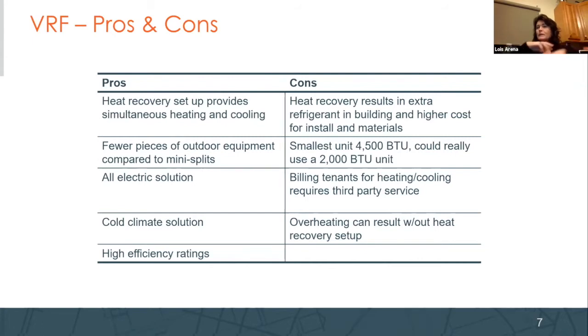So you need a heat recovery system to be able to achieve that. If you don't have that ability, you're basically in what they call heat pump mode, where you're either in heating or you're either in cooling if you're all on that same condenser. You can have fewer pieces of outdoor equipment with these systems because, like I said, one condenser can handle multiple terminal units on a floor. So you go up to 15, 20 units depending on the manufacturer. It's an all electric solution.